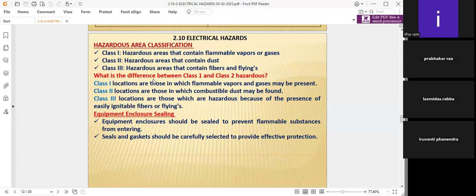If you consider a hazardous area, if this dust comes in contact with any electrical spark, there may be some fire, and an explosion may occur. That's what I'm saying, sir. The dust is flammable, and also combustible. Suppose dust is accumulated on the equipment for more time. Heat is generated on the equipment. After some time, definitely the dust will burn. What you said is 100% right, sir.